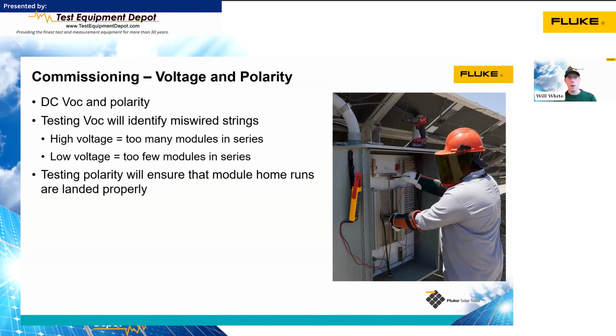If things are wired backwards, we can have current flowing through the circuit, which can cause problems when we go to open up fuse holders. They can arc and cause damage to the fuse holder. They could be a safety hazard, obviously, to the technician.